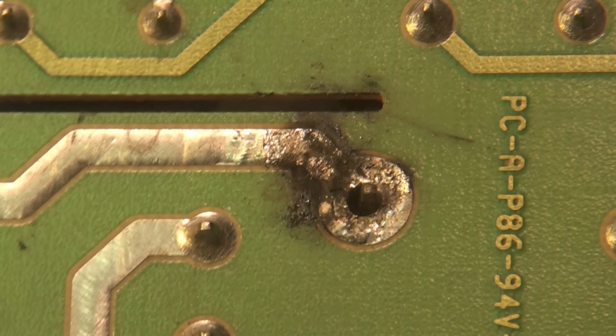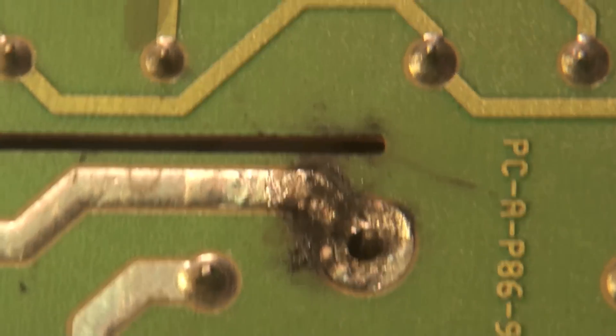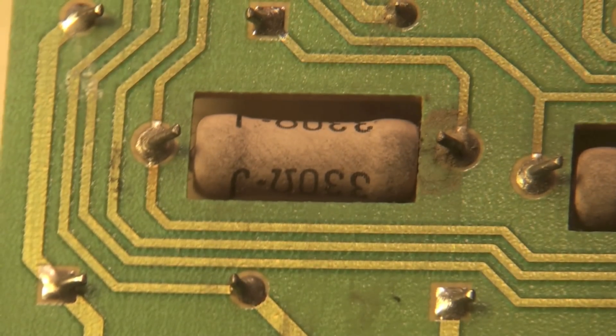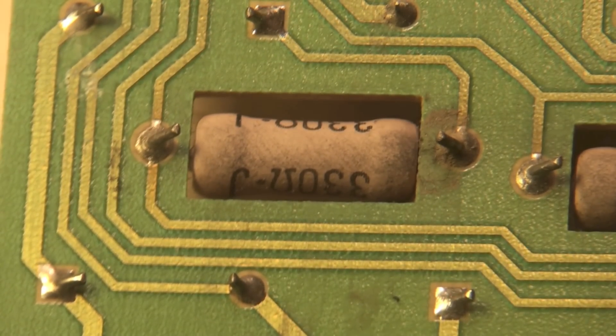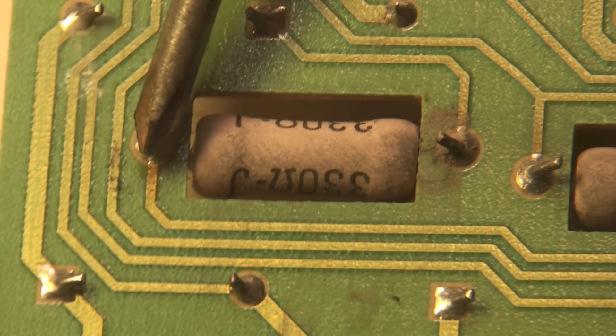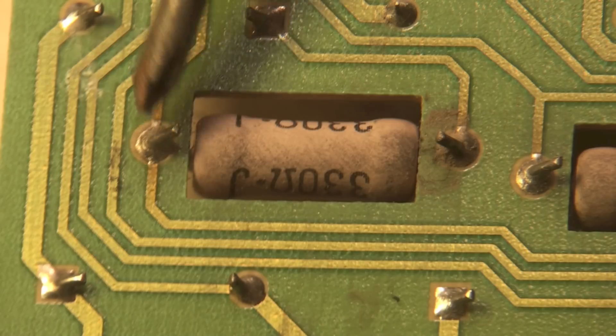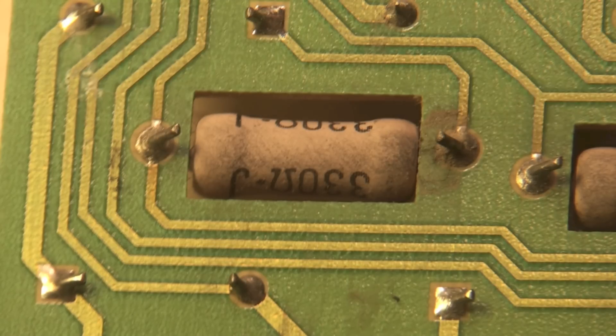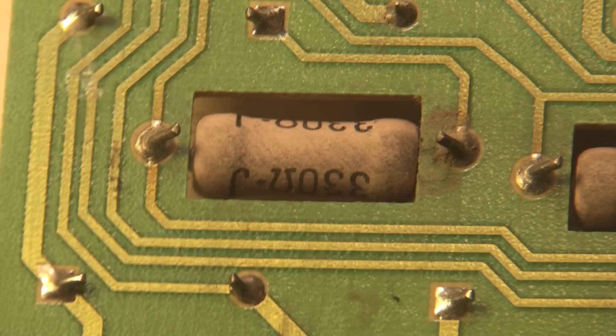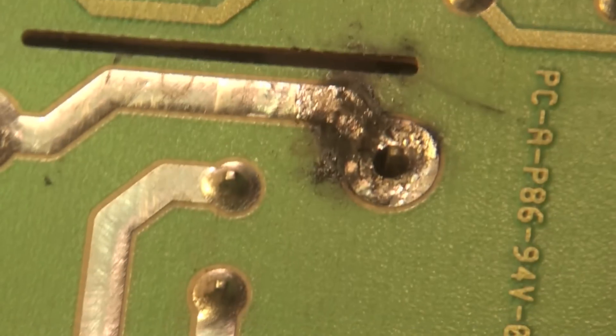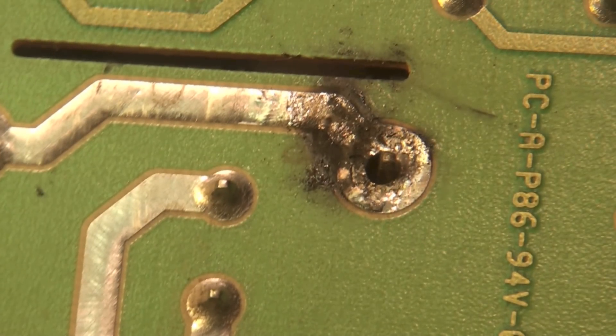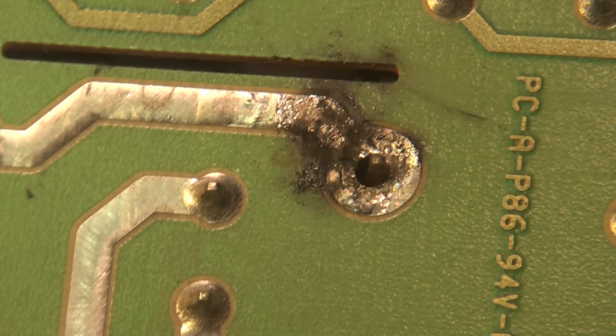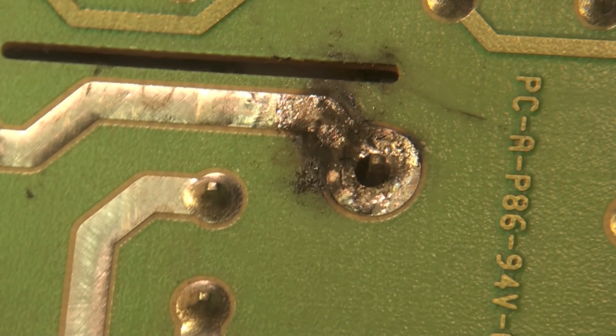Another place on the same board, right there, if you have haloing here on these board parts. I've talked about this before but I wanted to show you what the haloing actually looks like. That's what it looks like. It may not be burned around it, it may just have a little halo in there.